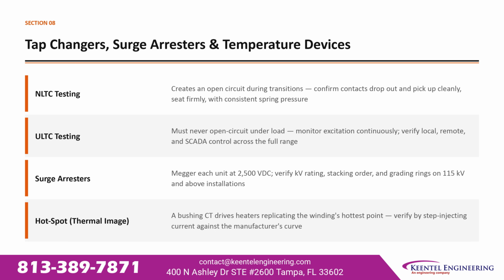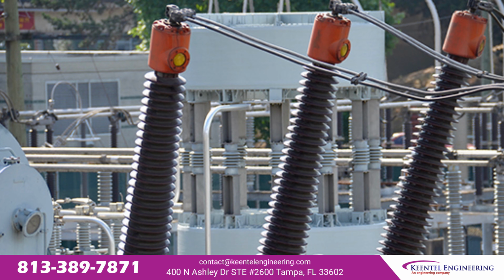Surge arresters get Meggered at 2,500 volts DC with verification of kilovolt rating, stacking order, and grading rings on installations at 115 kilovolts and above. And for hotspot or thermal image devices, a bushing CT drives heaters that replicate the winding's hottest point. Verify performance by step-injecting current against the manufacturer's curve.